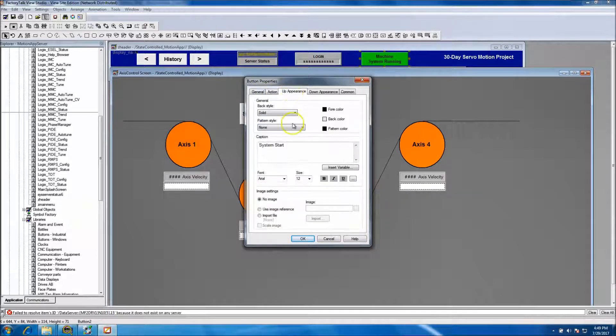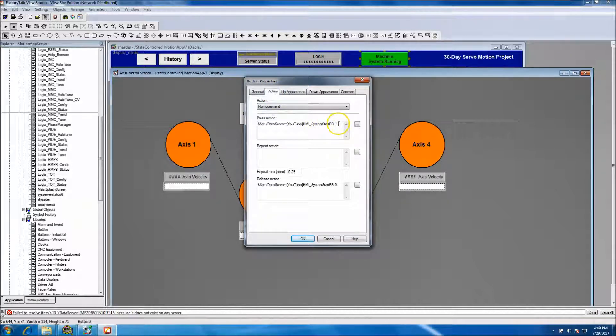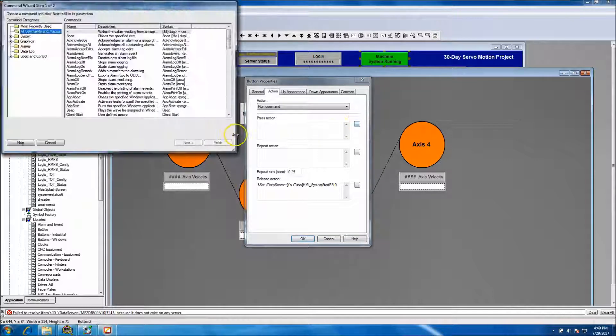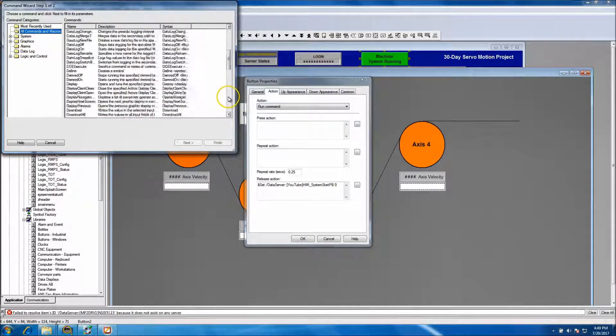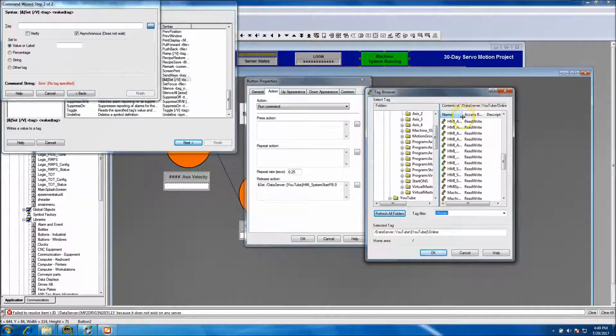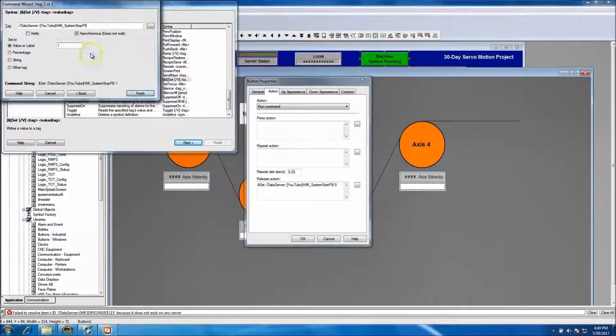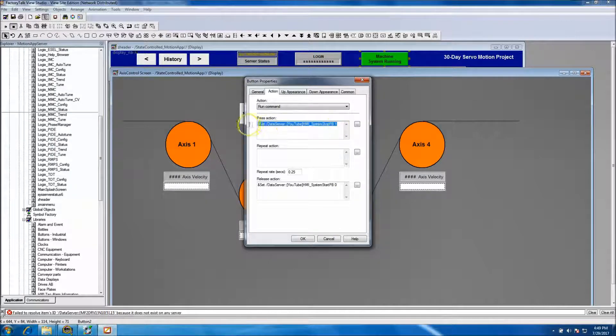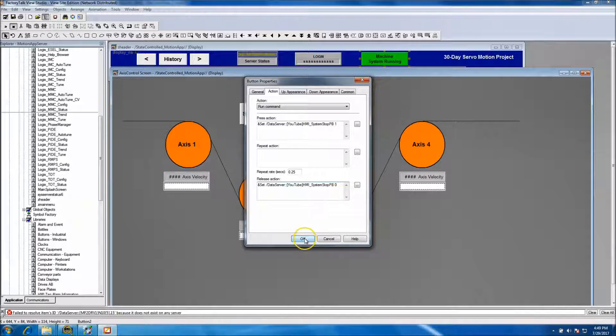Copy and paste and come back to do the name — this would be the Stop button. Let's scratch it and redo it so you can see the process: All Commands, go to Set, pick your tag. If you know the tag, enter it in. Set the value you'd like, see the full command string, hit Finish. Then copy it and paste it below and set to zero. I choose copy-paste because it's quicker.